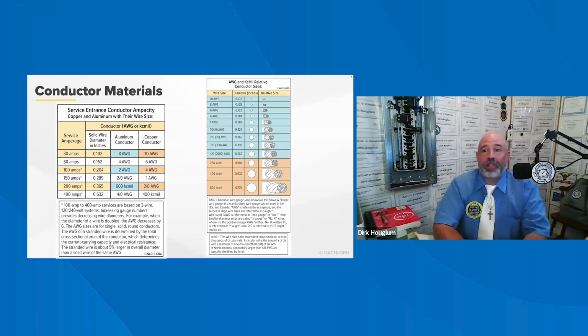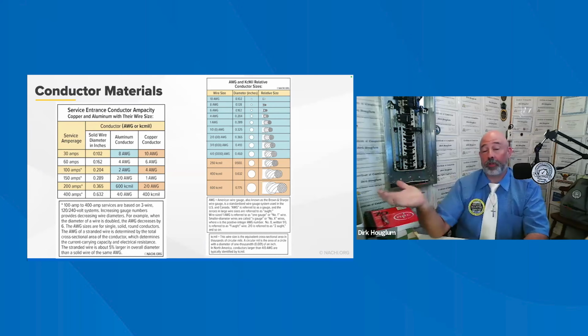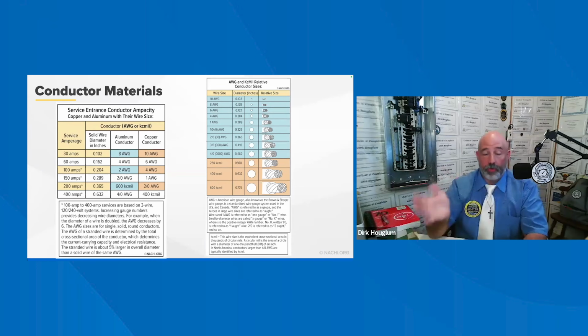Service entrance conductors, like all others, are made from either copper or aluminum. Aluminum conductors need to be a larger size than copper for any given amperage. We've talked about this. Aluminum terminals may also be coated with an antioxidant. We saw that in the video, and that helps prevent the corrosion of the metal, although the more recent AA-8000 aluminum alloy conductors do not require it. So there is certain aluminum that doesn't need it and some that do. So when in doubt, further evaluation.